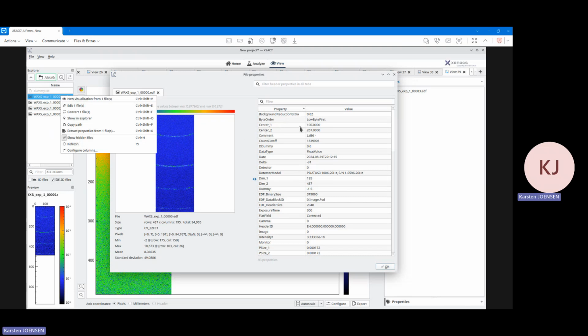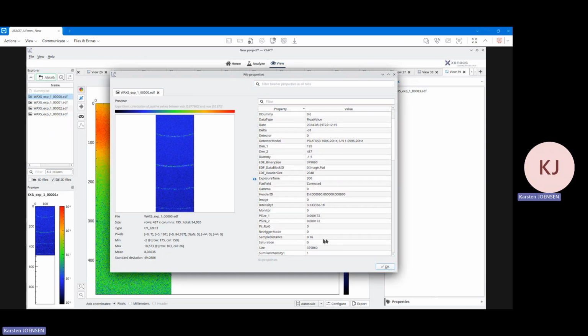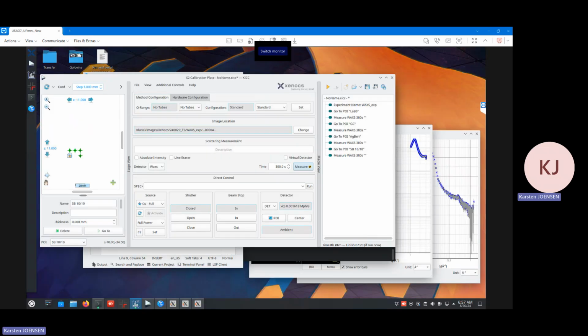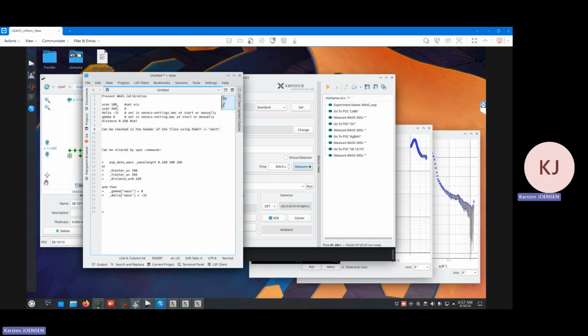Now, the ones I'm looking for are center 1 and center 2. You can see those are 100 and 267. And then I'm looking for the gamma and the delta value. So the delta value is here, -31, and the gamma value is 0. And then the sample distance is 0.16. Let me jump back to the other screen. Now those parameters are here. Let me just correct that. That was 267. So these are preset.